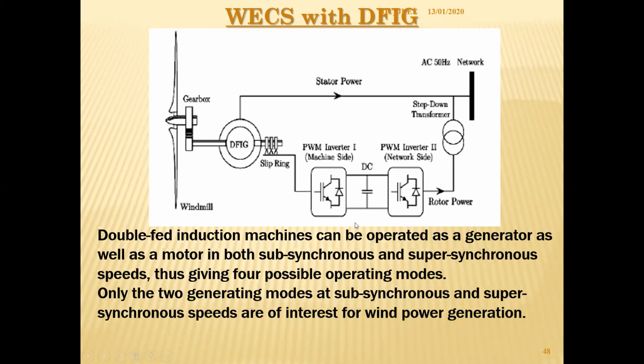Now if we are able to vary the rotor resistance to a large extent with this, that means the effective rotor resistance seen by the rotor can be of the order of say 30 to 35% even. So it can operate at a slip of 30%, 35%.